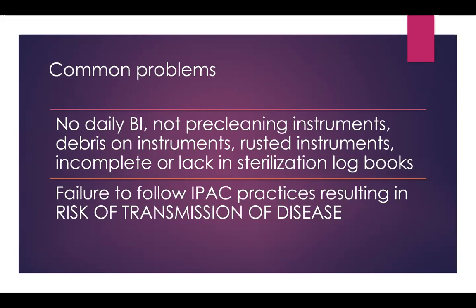Other common problems include rusted instruments and incomplete or lacking sterilization logbooks — logbooks are very important. At the point of care, any glass ionomer cement, temporary cement bond, or anything that sticks on the surface before it gets to the reprocessing area needs to be wiped down. An alcohol gauze should be sufficient.